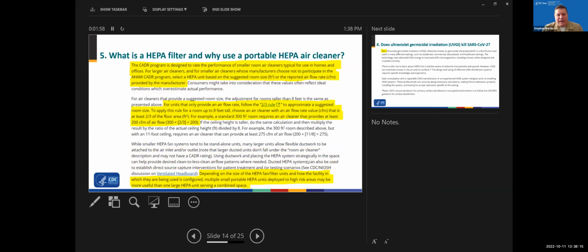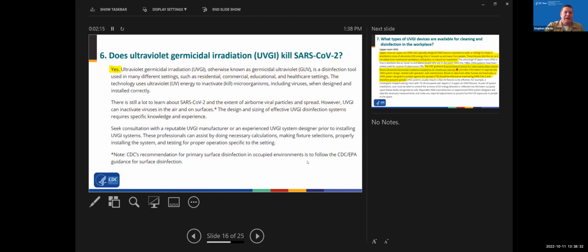And one other thing that I want to point out is that depending on the size of the space, you don't have to just get one HEPA unit for that space. Sometimes it makes more sense to get 2 or 3 and spread them around the room, instead of having all that air being pulled and exhausted back into the space in one corner setting.